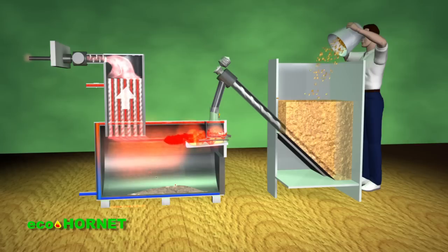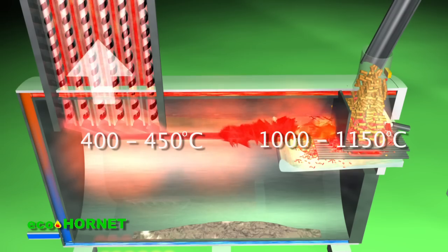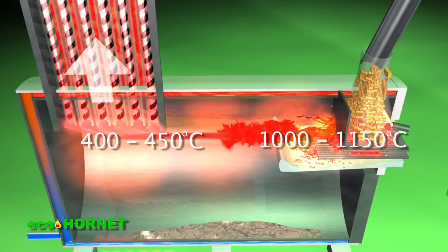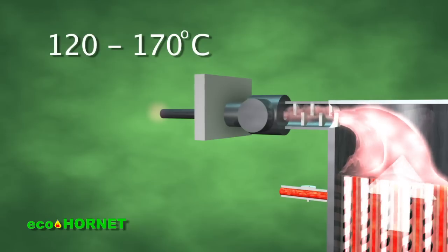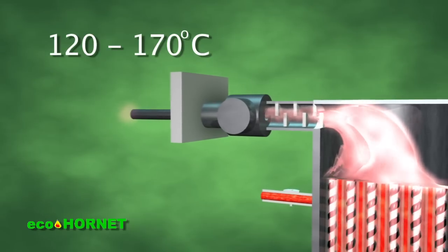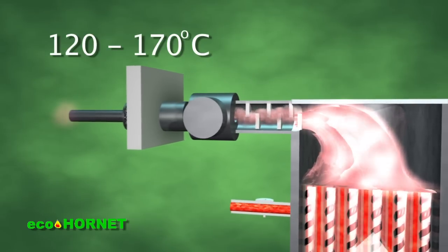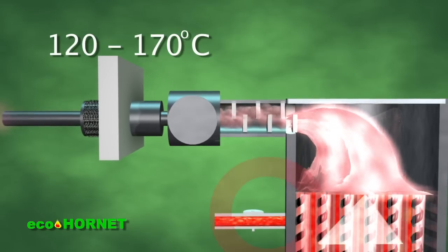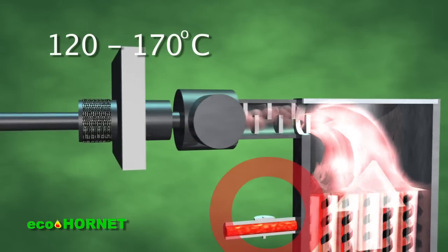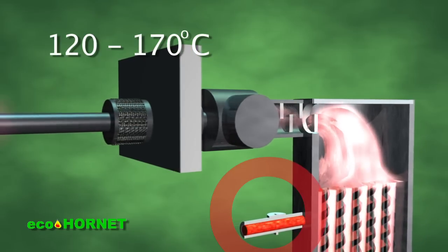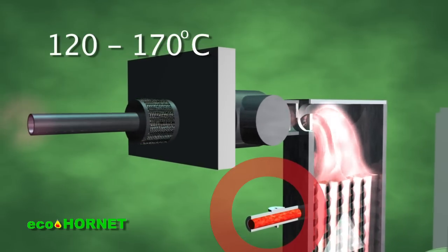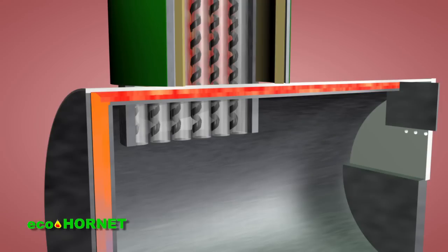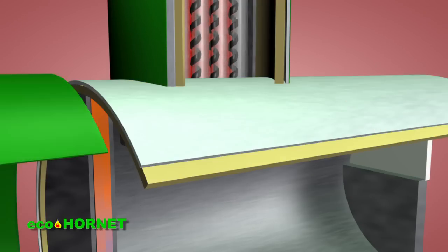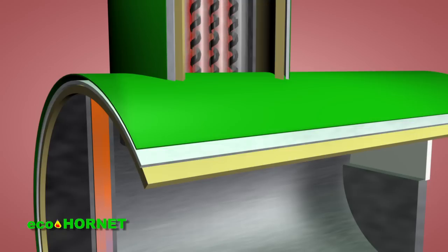The burnt gas temperature in the exhaust circuit varies. It reaches 1000 to 1150 degrees Celsius at its exit from the burner, 400 to 450 degrees Celsius upon entry in the convection area, and 120 to 170 degrees Celsius upon its release into the atmosphere. The surface of the outgoing pipe for the heating agent is provided with a temperature thermocouple, providing information which is retrieved and processed by the automation system. The heat exchanger is heat insulated with aluminized mineral wool and is placed in a metallic or fiberglass housing, whose outer surface temperature does not exceed 35 degrees Celsius.